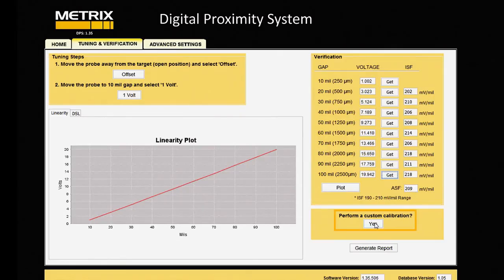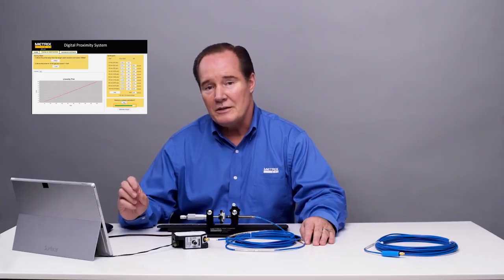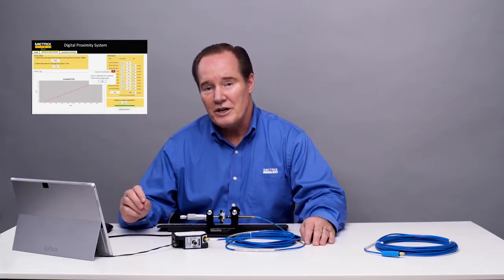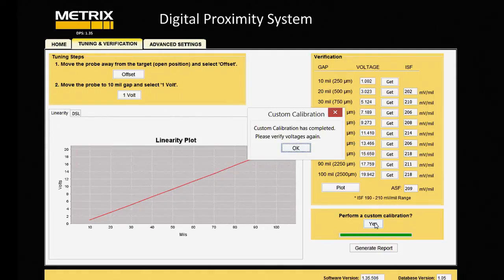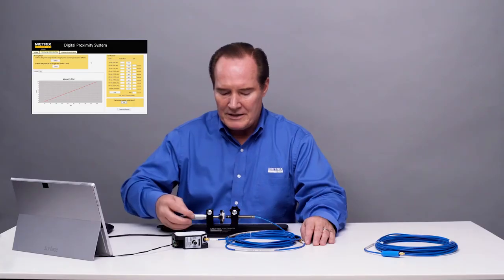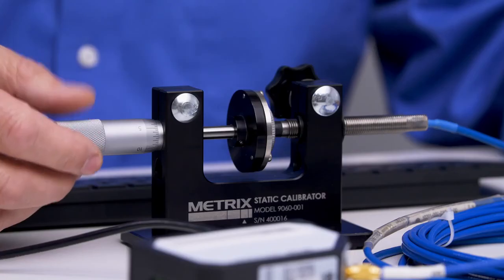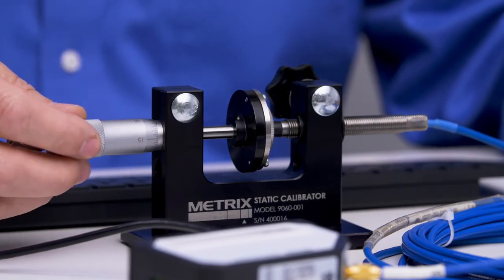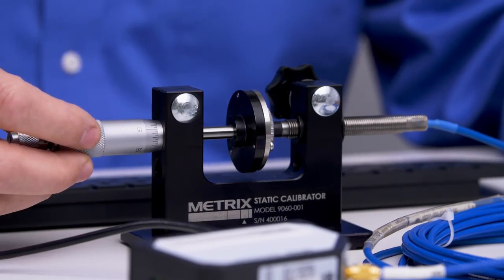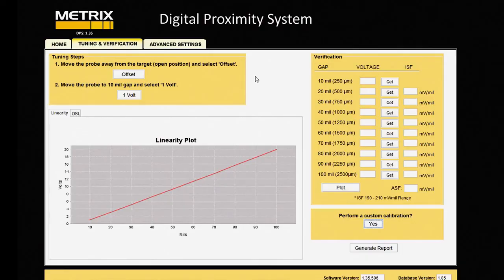So we'll go ahead and perform a custom calibration by hitting yes. And after it updates using the voltages that we just took, it will update the configuration inside the digital proximity system, and then we'll re-verify to see if we get a better result. So we'll go back to 10, and we'll go ahead and take data again, just like we did before.